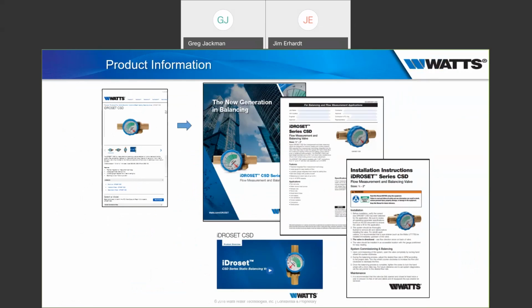Not at this time. The iDROSET currently is intended for your typical hydronic system, which is going to be water, or a water propylene glycol mix, with whatever additives or treatments are typically used in hydronic systems. At this point in time, we do not have a stainless steel version that would be suitable for chemicals or any liquid that would be aggressive to brass. So it's all basically hydronic, heating or cooling, and in Q1 of next year, potable water for recirculation systems.